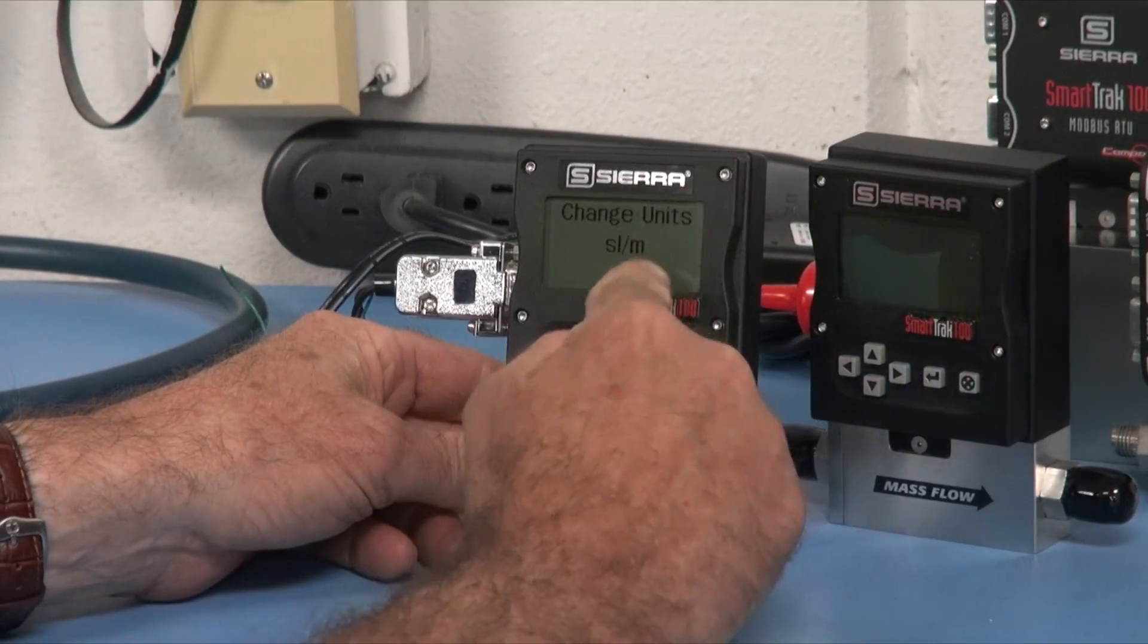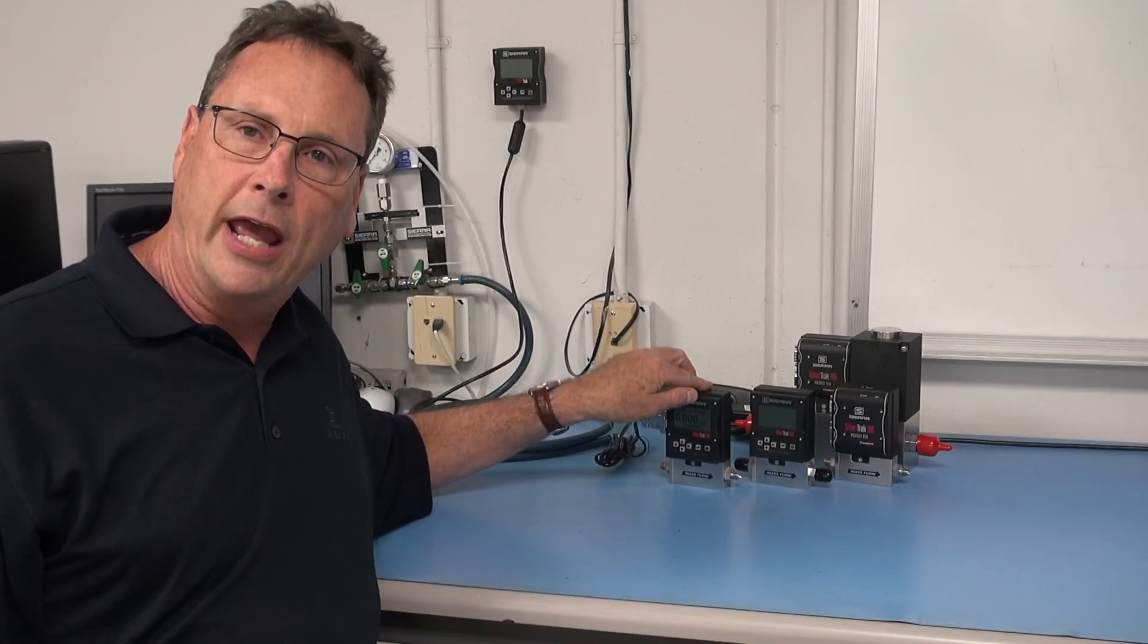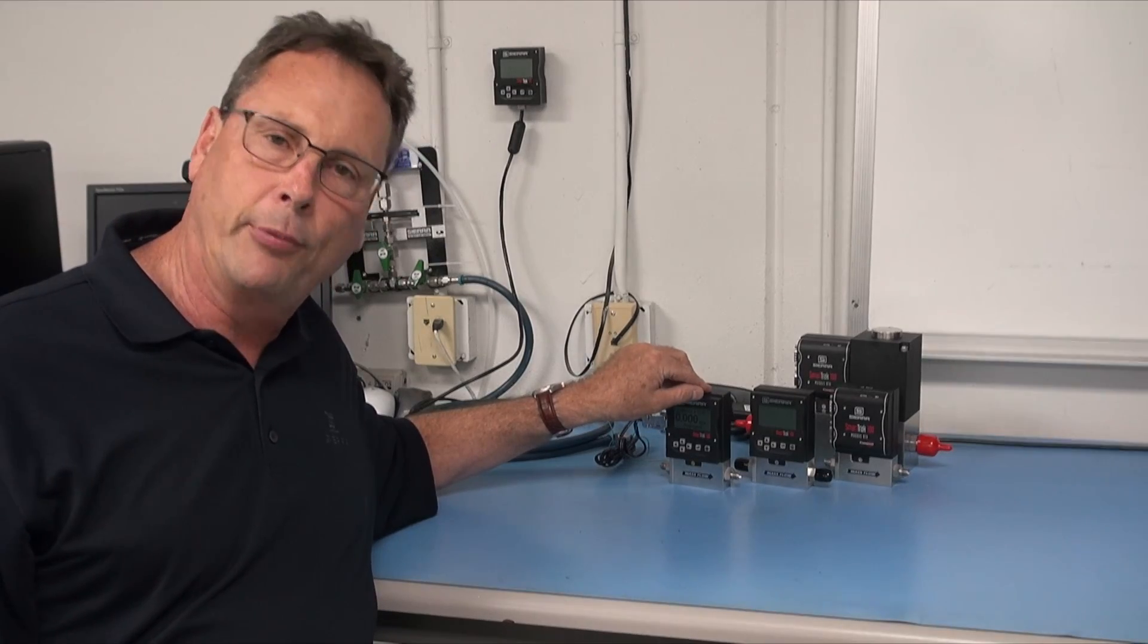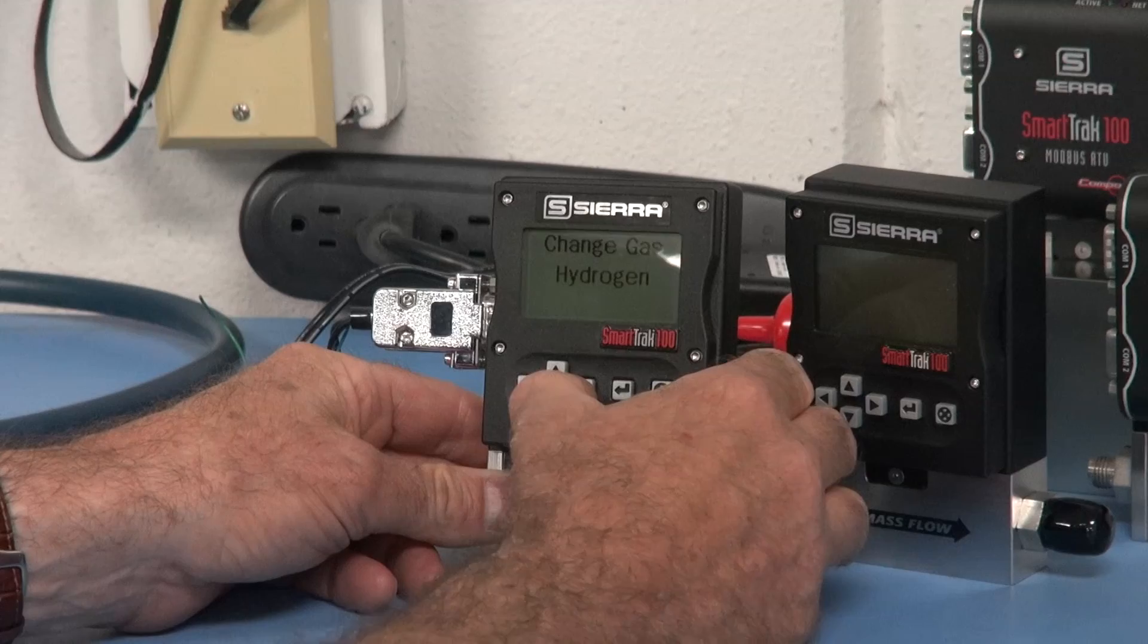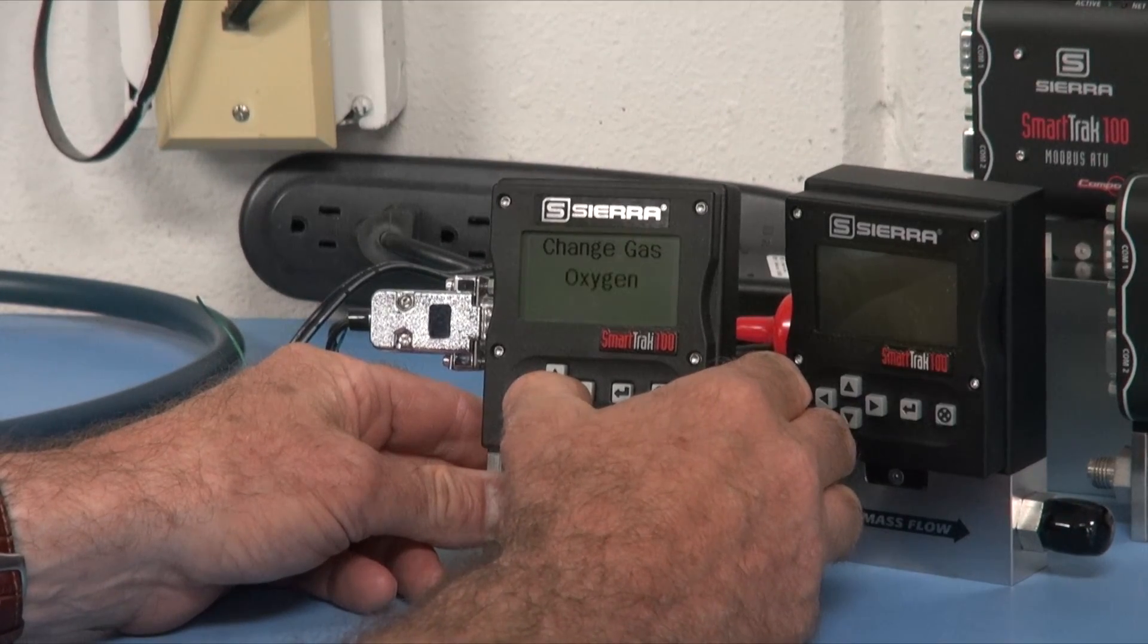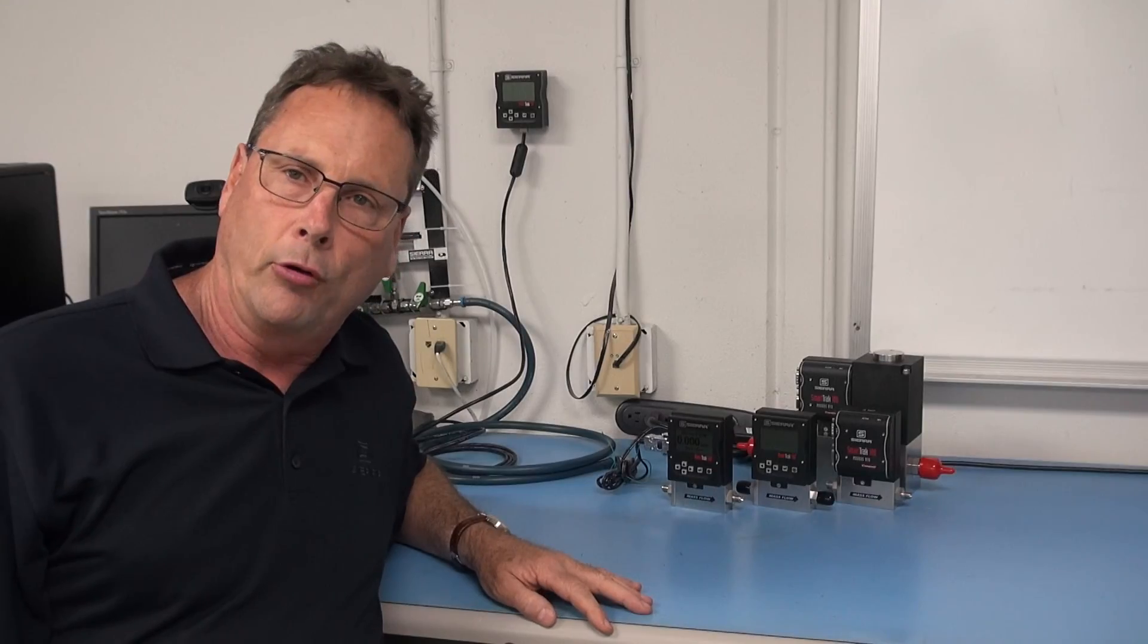We can change the units, so this would have to be set up in standard liters a minute, but the SmartTrak 100 has 10 gases that can be pre-programmed. It says hydrogen, but if I press enter I can scroll and choose methane, nitrogen, nitrous oxide, oxygen, air, etc. Or you can tell us your special mixture and we can pre-program that.